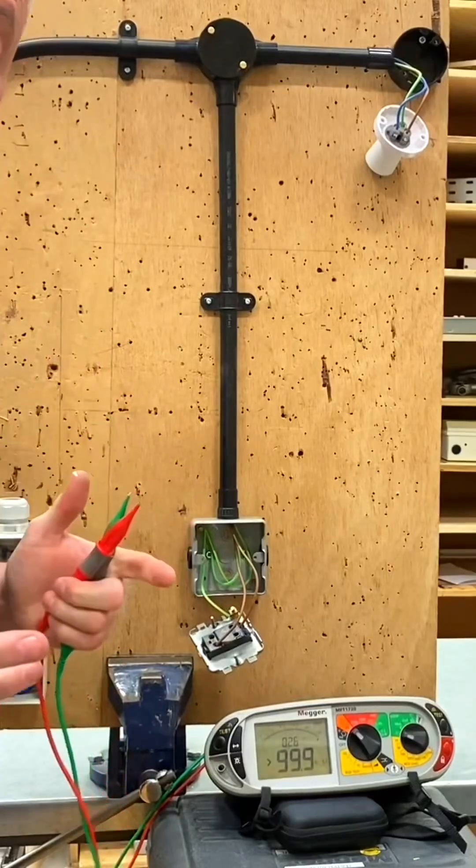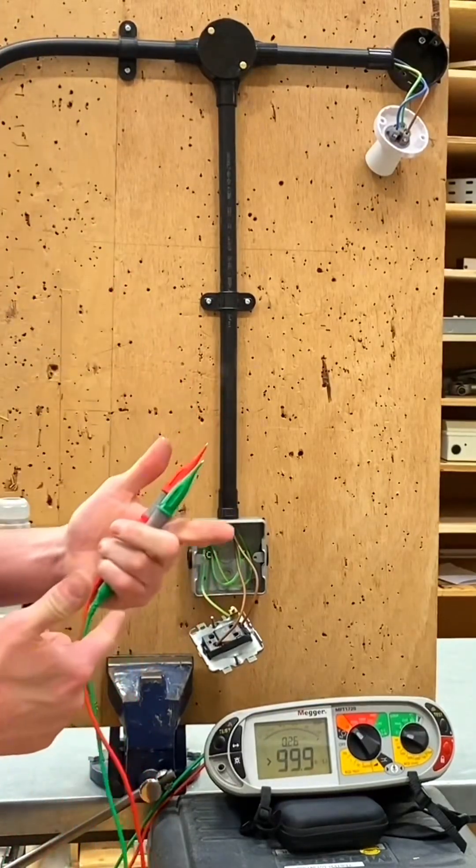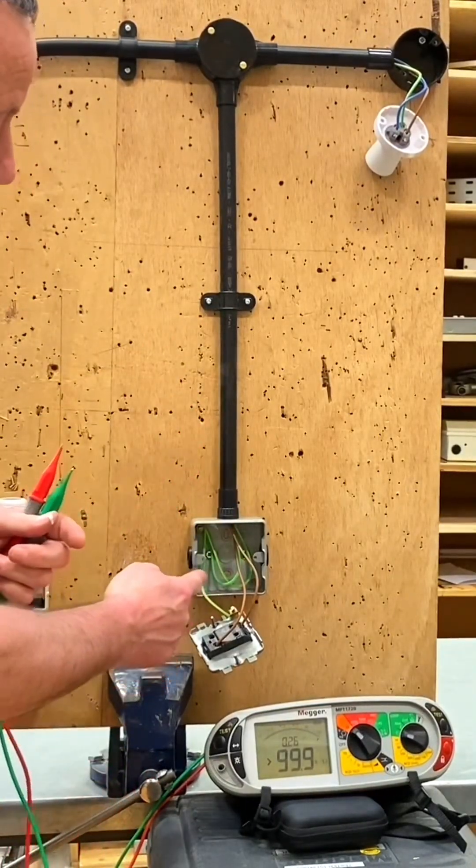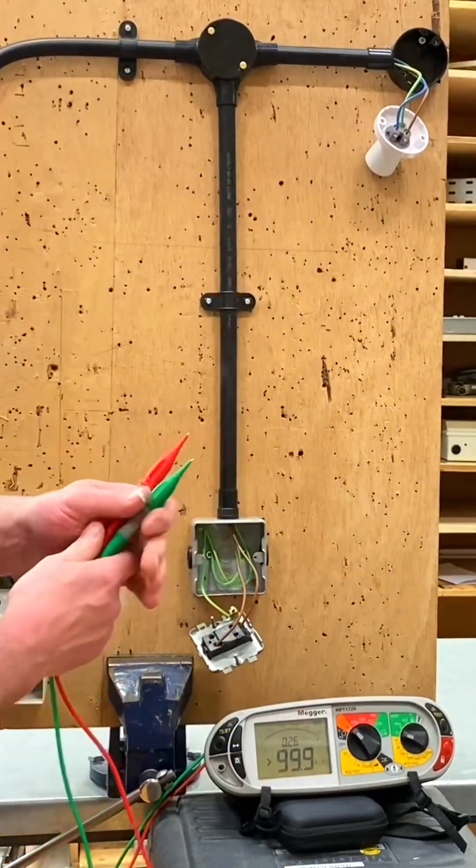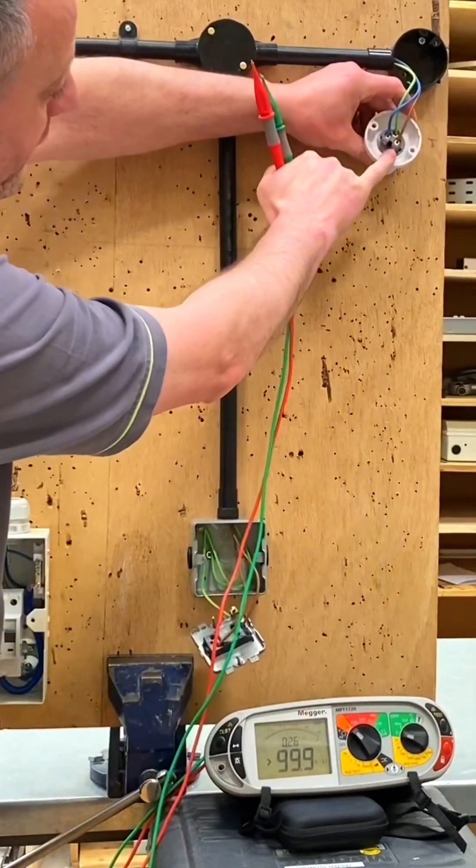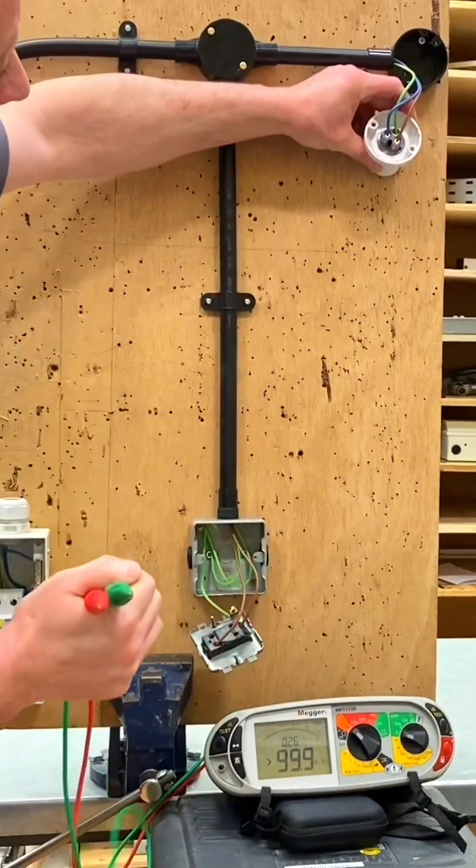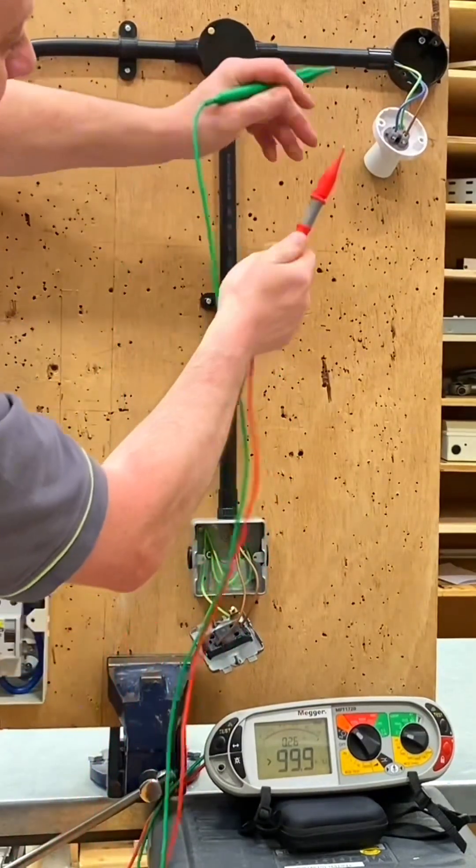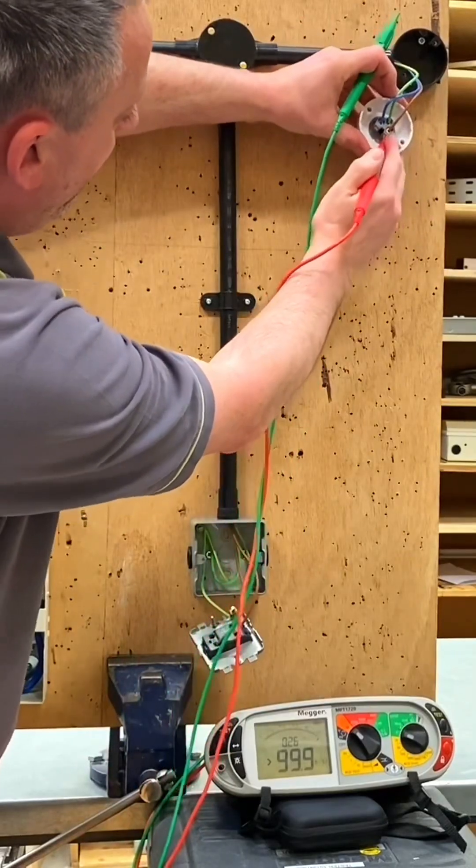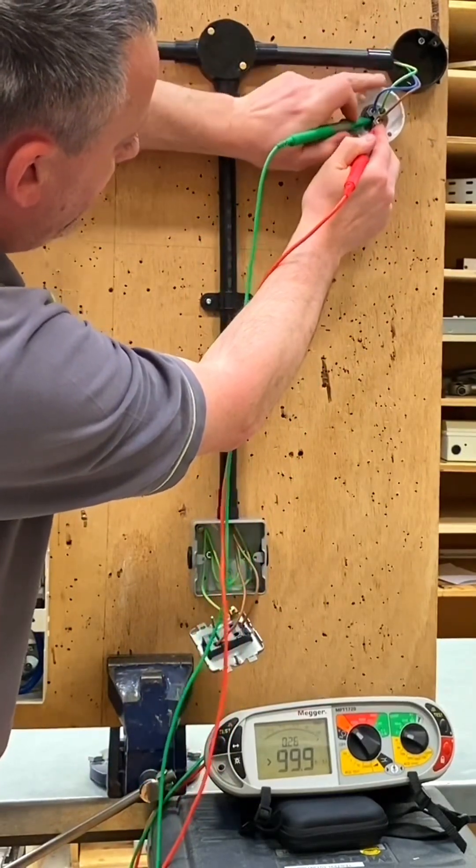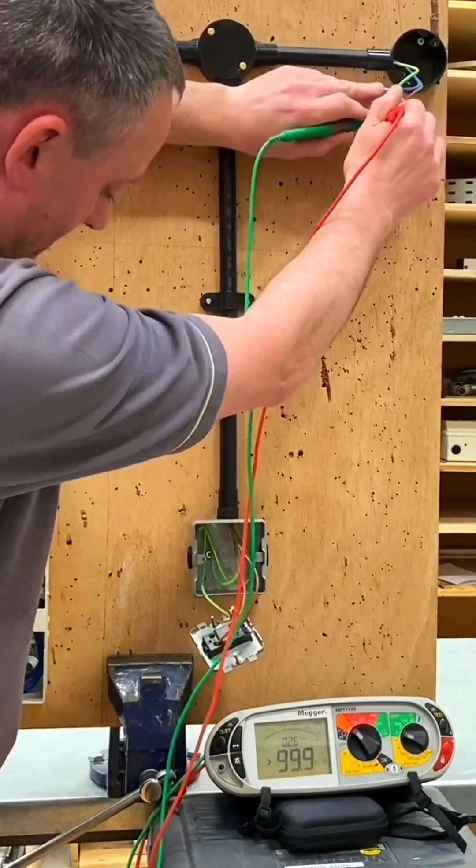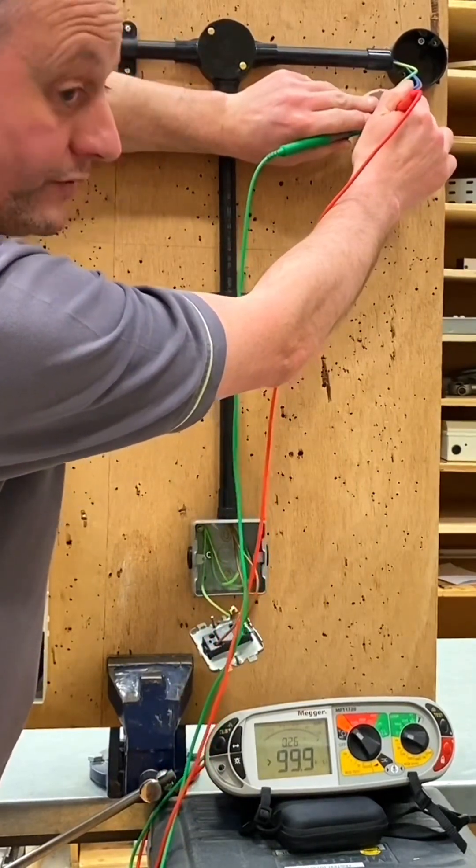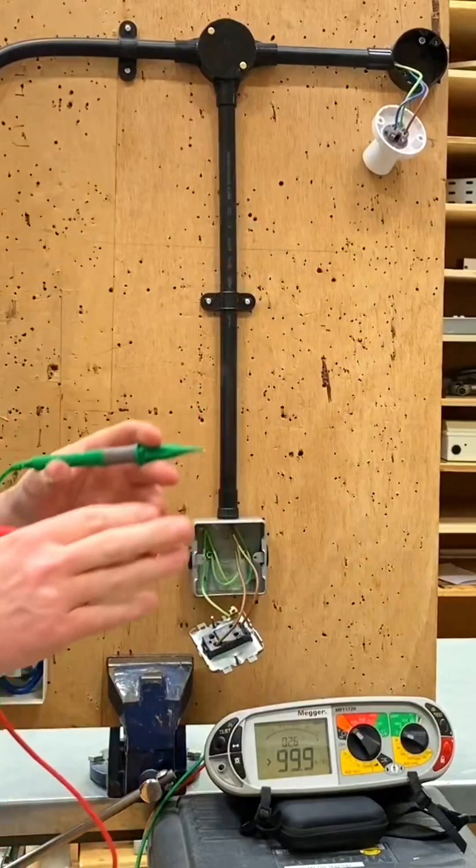I've pulled the camera back so you can see the operator switch and the full scale deflection of the instrument. I'll talk you through where I'm probing. We're probing into the line and CPC in the fitting itself. If I go line and CPC first, we have no reading whatsoever. You can start panicking, or you can think - is the switch in the off position?